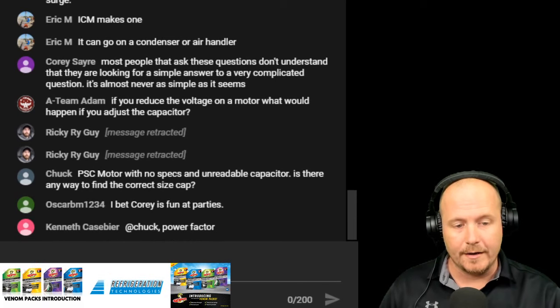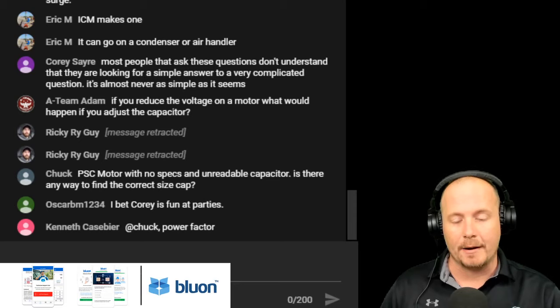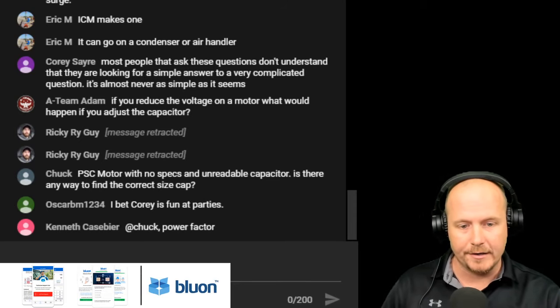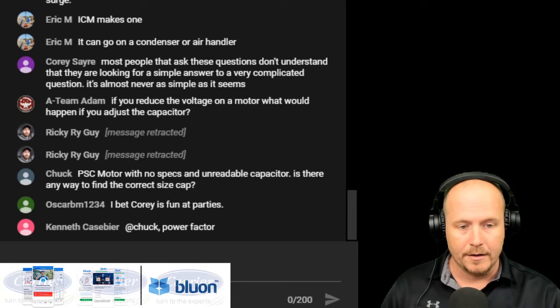I would put one in, then use a power quality meter like the Redfish or the new Field Piece, look at my power factor, and just keep adjusting until I get to 1 or as close to 1 as I can.